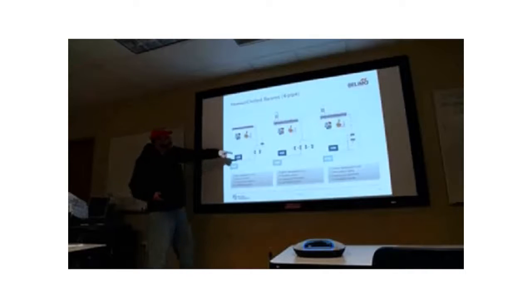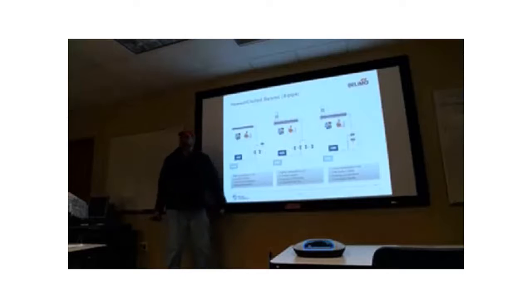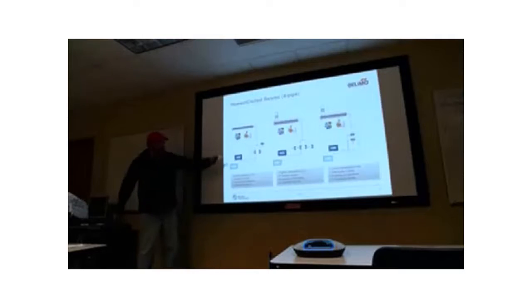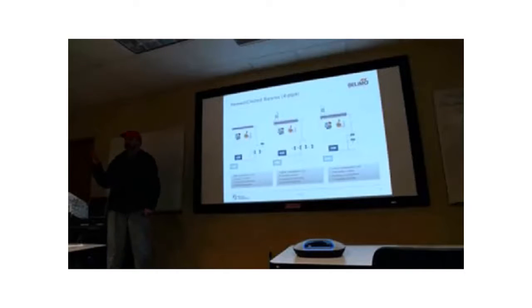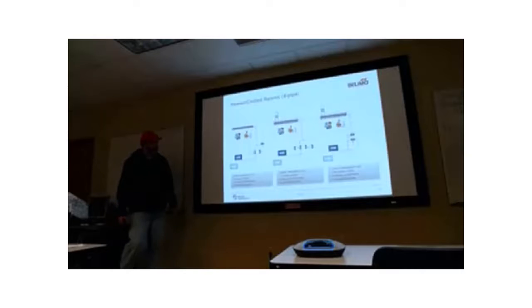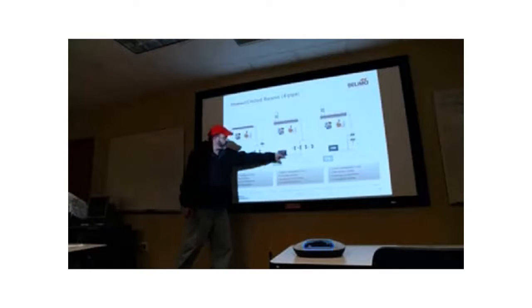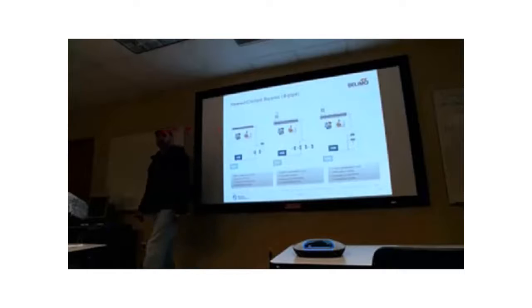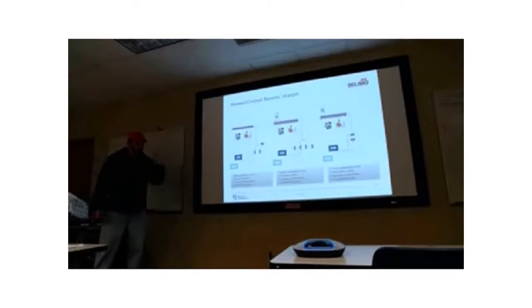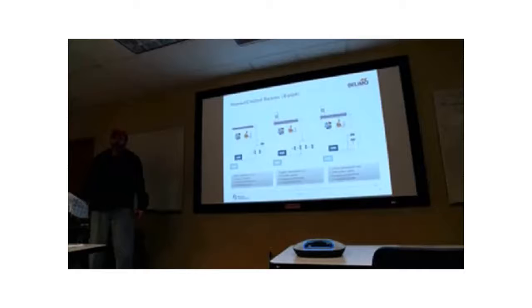That's one scenario. The Cadillac deal is this one, which isn't done as much anymore. Now what you have there is 2 switching valves or 2 on-off valves, and then 2 proportionally controlled valves. So you're controlling the water through the beam like a coil that way. So now you got 8 piping connections, 4 valves, and 4 control connections. I don't know if you guys see where I'm going here. So you got this, you got this. Both of these are equivalent to that: 1 six-way valve, 1 control connection, 6 piping connections.